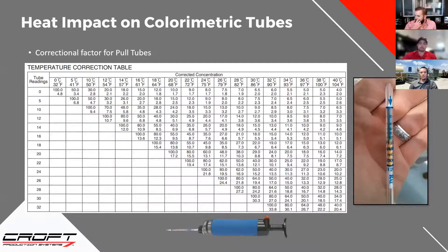The Sensidyne tubes have the highest correction factor. The Ray tubes definitely have some correction factor too. Typically, the warmer the gas, the lower the actual reading compared to what the tube shows. The same thing also applies to CO2 and H2S tubes — they all have a temperature correction factor. The water content ones are the ones where we see the most impact between what's being pulled and what the real reading is once you apply the correction factor.